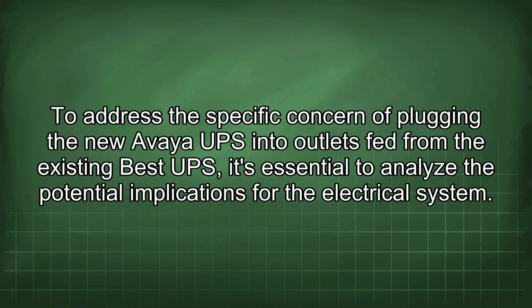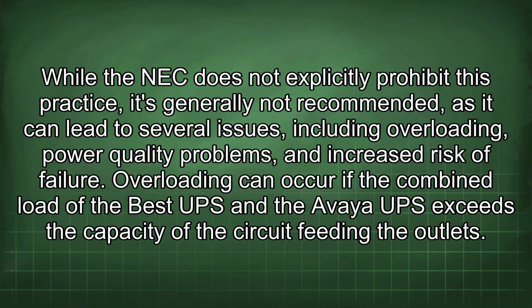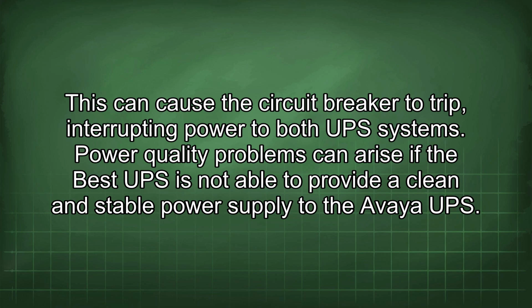To address the specific concern of plugging the new Avaya UPS into outlets fed from the existing BEST UPS, it's essential to analyze the potential implications for the electrical system. While the NEC does not explicitly prohibit this practice, it's generally not recommended, as it can lead to several issues, including overloading, power quality problems, and increased risk of failure. Overloading can occur if the combined load of the BEST UPS and the Avaya UPS exceeds the capacity of the circuit feeding the outlets. This can cause the circuit breaker to trip, interrupting power to both UPS systems.